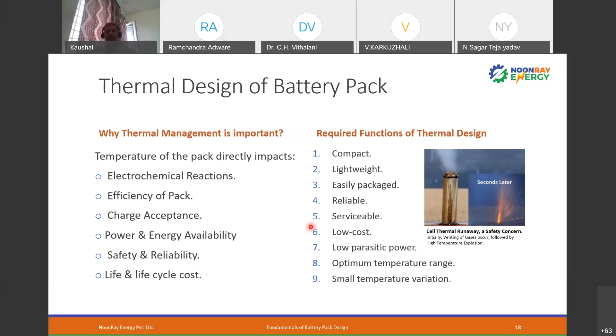What happens at high temperature? Primary concerns are thermal runaway and non-uniform aging effect. If one cell in the pack is working at 35 degrees and another at 50 degrees, I have a temperature differential. With that differential, one cell could age faster than the other. We don't know exactly, but that could be a reason. So we have to minimize the non-uniform aging effect as well. Cooling is required during hot environment, moderate to large current demand, and fast charging. We'll come back to moderate to large current demand. Fast charging is again putting more current into the battery. That's how fast charging happens.